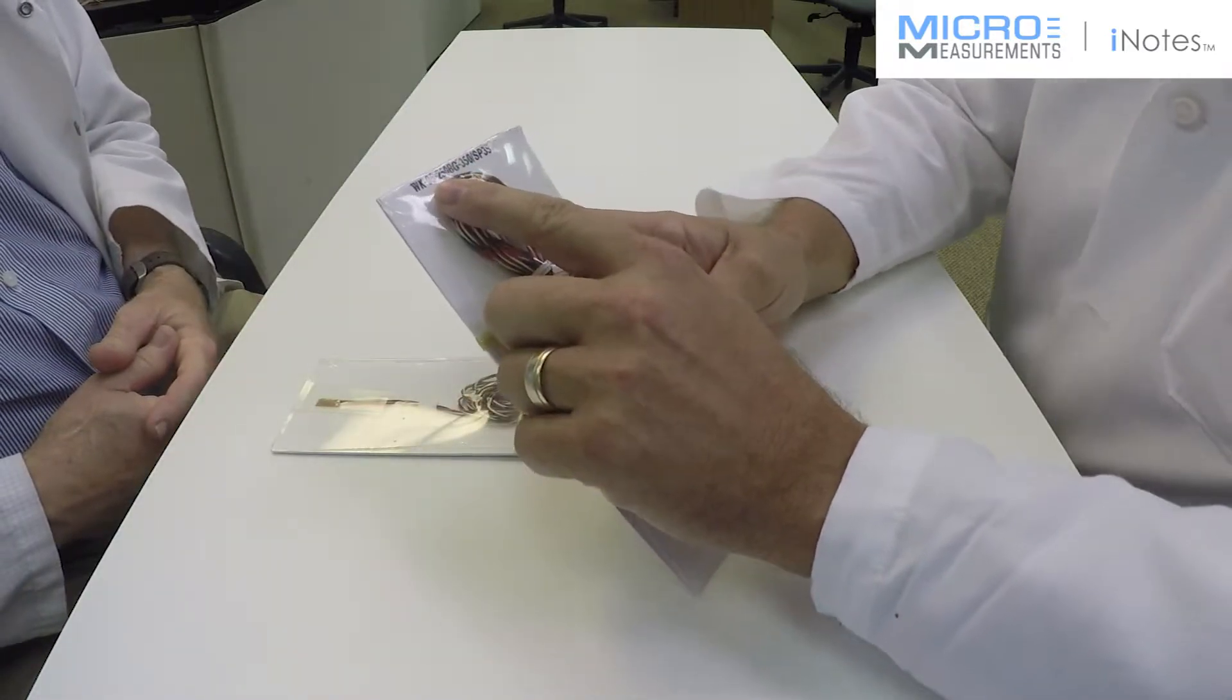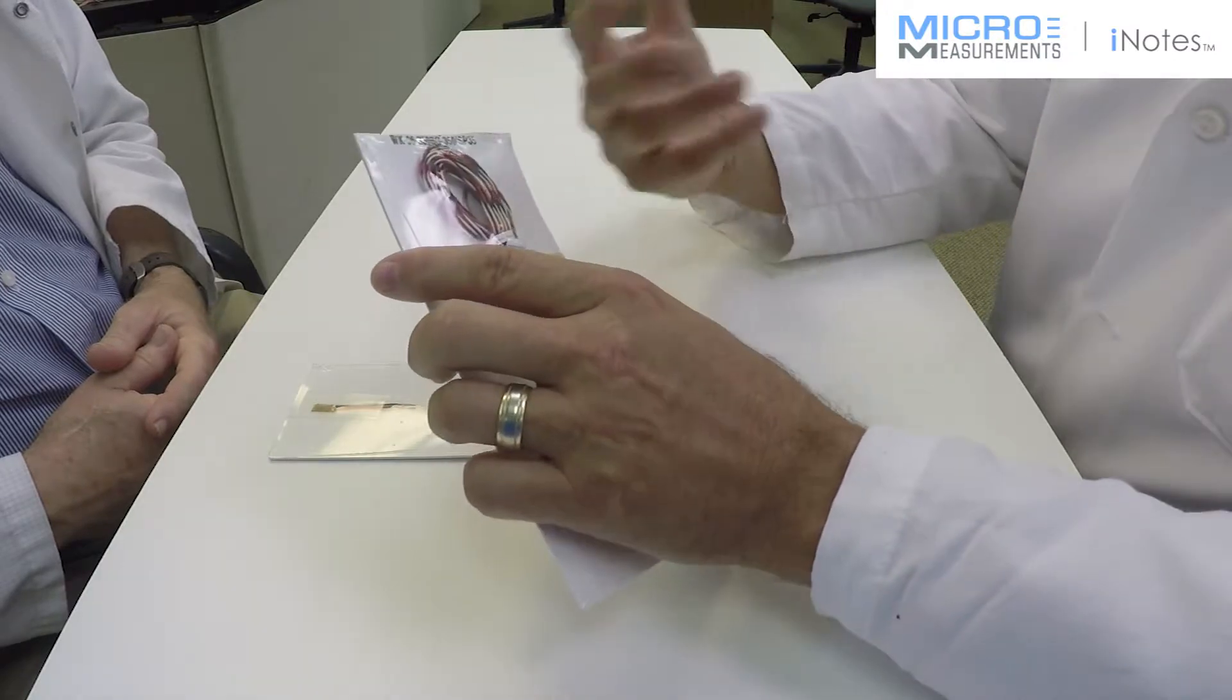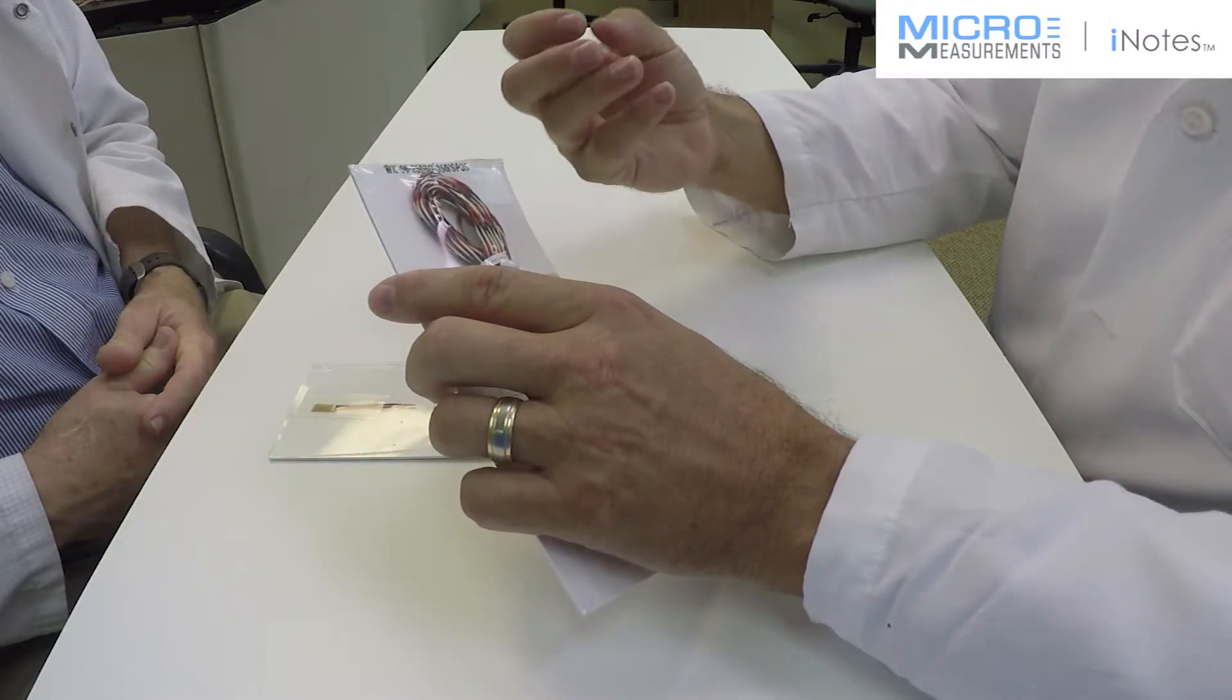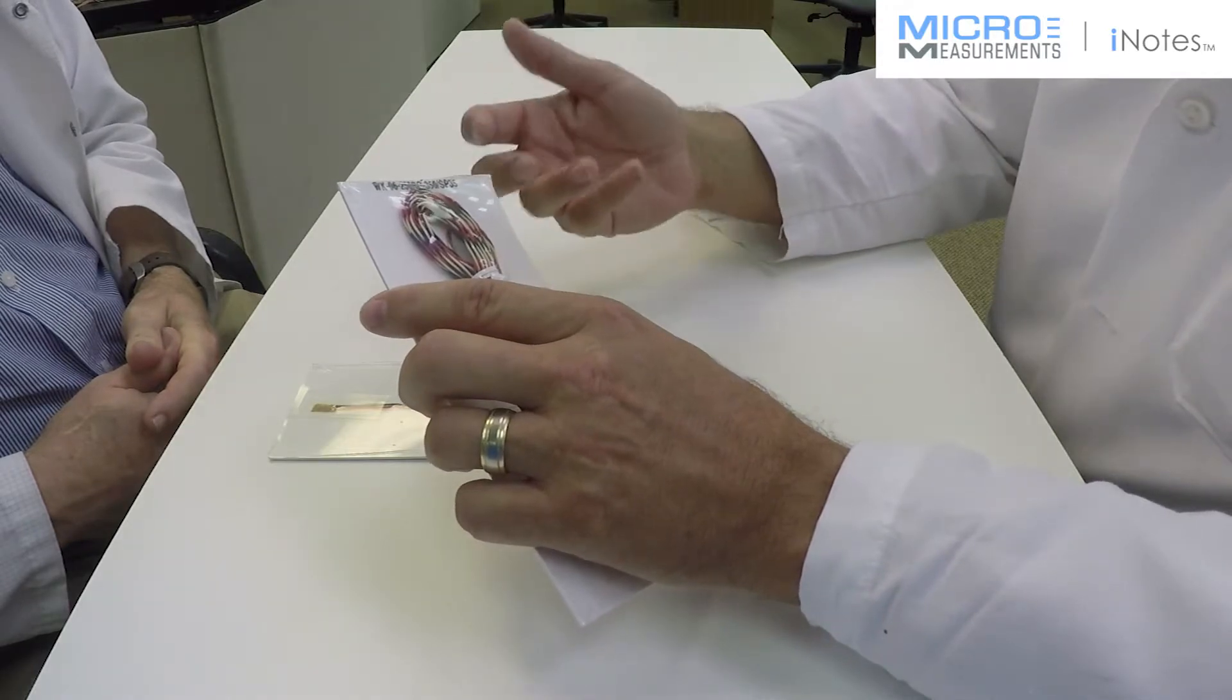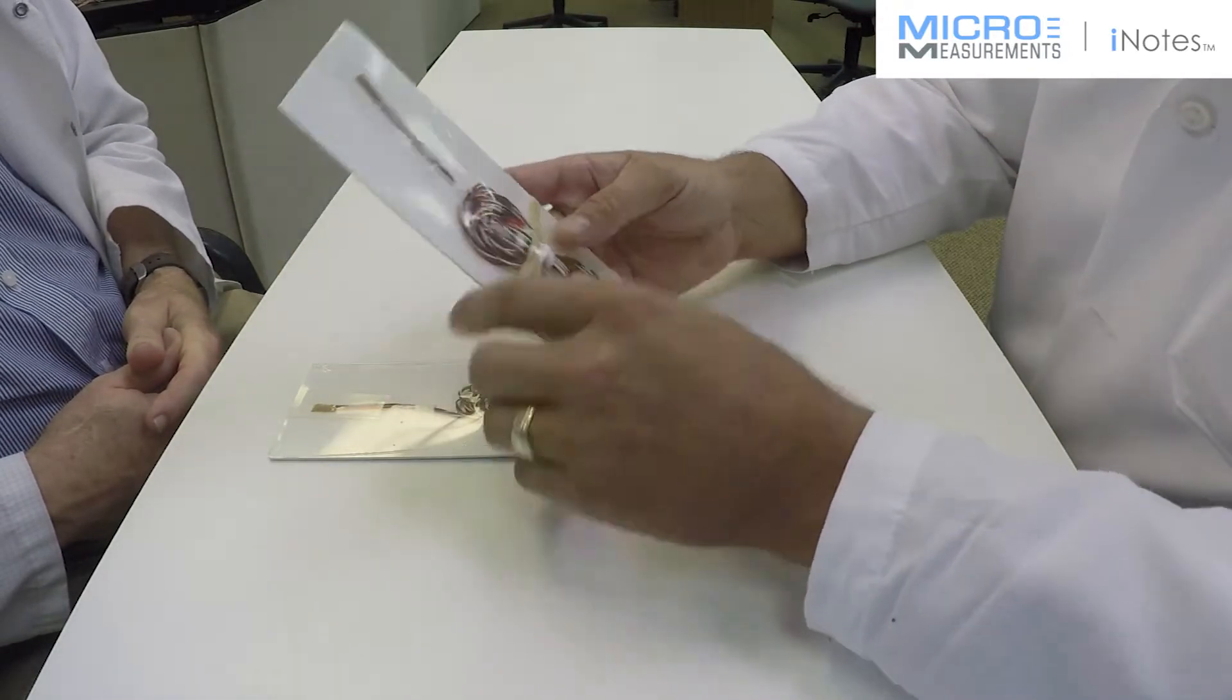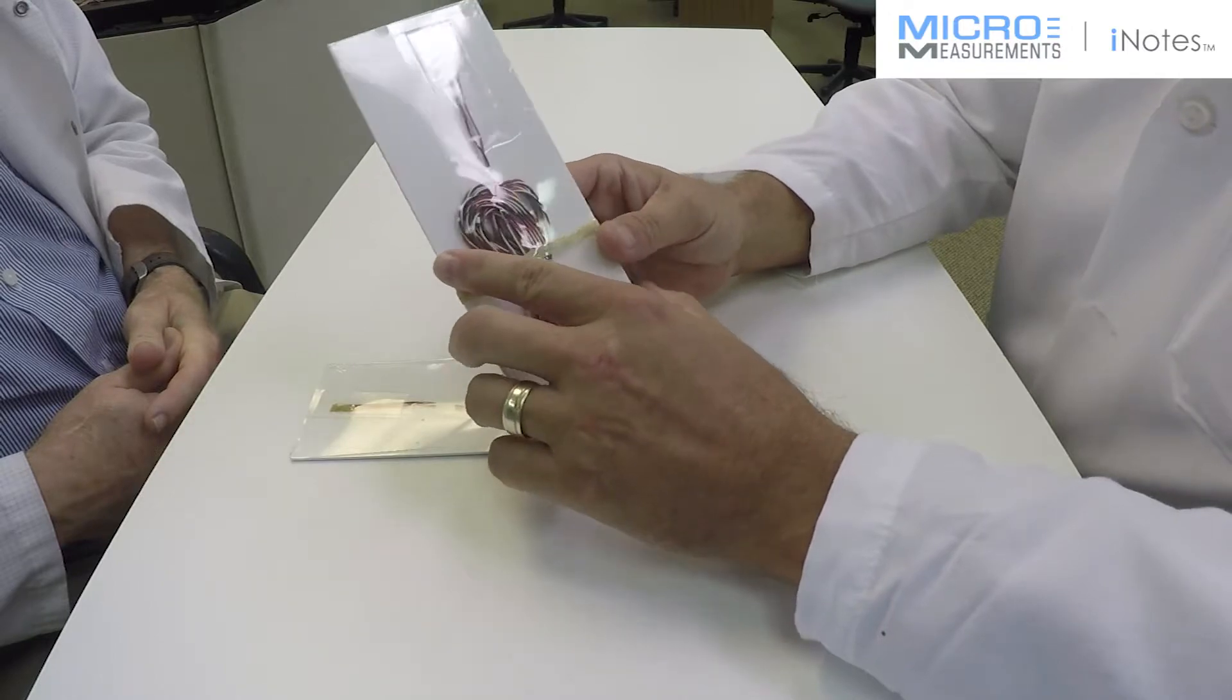When you take a WK series gauge, they have a glass epoxy phenolic backing material and the Karma foil. And that's going to be rated to a higher temperature. So with this combination, you can push it right up to about 450 degrees Fahrenheit.